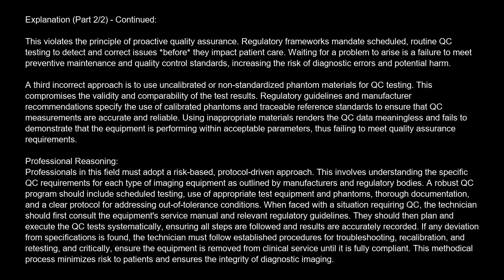When faced with a situation requiring QC, the technician should first consult the equipment service manual and relevant regulatory guidelines. They should then plan and execute the QC tests systematically, ensuring all steps are followed and results are accurately recorded. If any deviation from specifications is found, the technician must follow established procedures for troubleshooting, recalibration, and retesting, and critically, ensure the equipment is removed from clinical service until it is fully compliant. This methodical process minimizes risk to patients and ensures the integrity of diagnostic imaging.